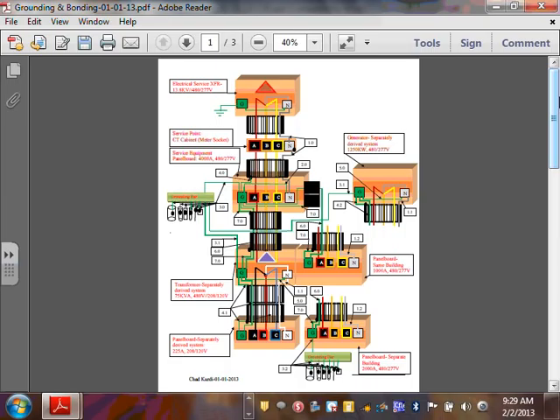The reason I picked that one, as we all know, is that if you go to a different building, there are rules and regulations for bonding and grounding for a separate building. Okay? Then, to spice it up, I threw a generator at the top here. If that's not enough for you, I pulled the neutral from the generator, and I ran it as a separately derived system. So I have another generator that I'm running as a separately derived system. I'll say a few things about generators when we come to it.